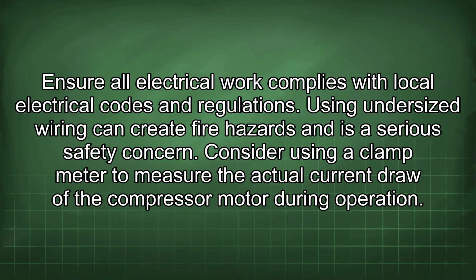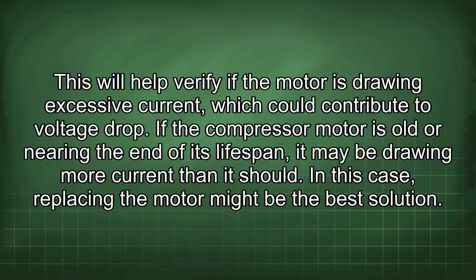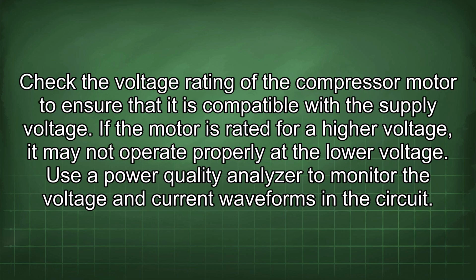Consider using a clamp meter to measure the actual current draw of the compressor motor during operation. This will help verify if the motor is drawing excessive current, which could contribute to voltage drop. If the compressor motor is old or nearing the end of its lifespan, it may be drawing more current than it should. In this case, replacing the motor might be the best solution. Check the voltage rating of the compressor motor to ensure that it is compatible with the supply voltage. If the motor is rated for a higher voltage, it may not operate properly at the low voltage.